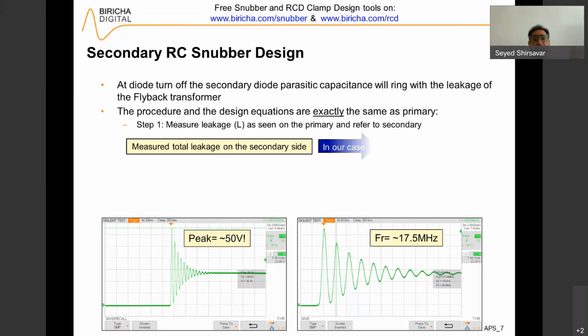The procedure for the design is exactly the same. So step one, you measure the leakage as seen on the primary with reference to secondary. We have done this in various videos with Omicron, and we have used the Bode 100 to measure our transformer. Our measured total leakage on the secondary side is 215 nanohenries, mainly because it's a 1-to-1 transformer ratio. If you had a 10-to-1 ratio, that would have to get reflected back with the square of the turns ratio. Again, we have done a video that explains exactly how that is done. But for simplicity, let's say that we know the leakage, which is 250 nanohenries.